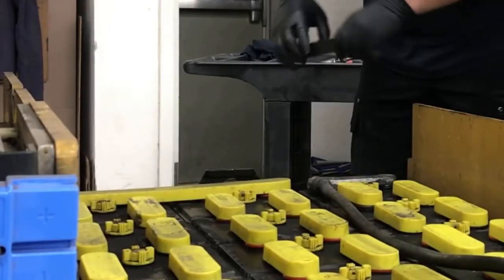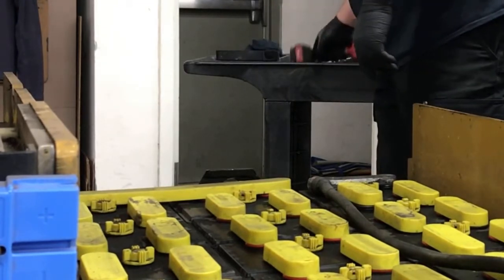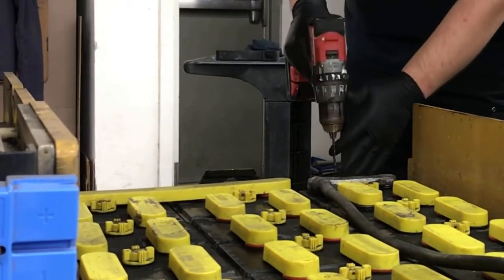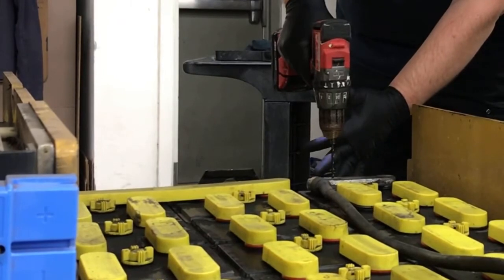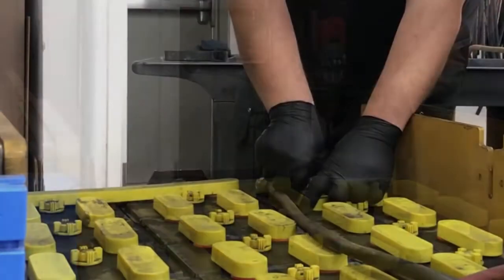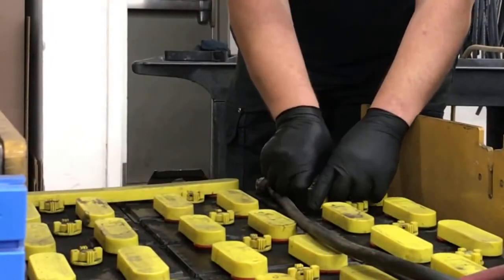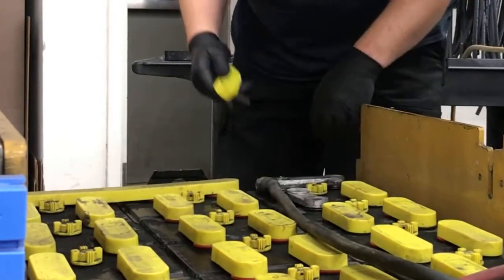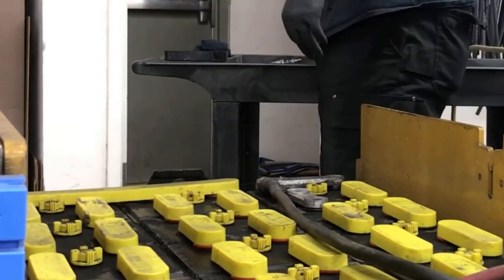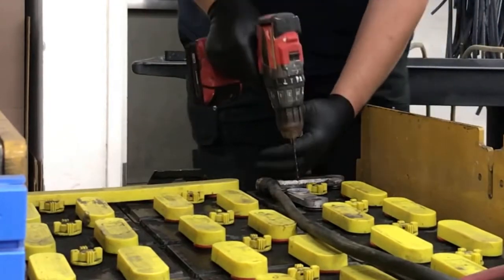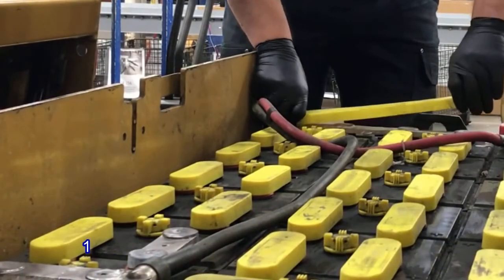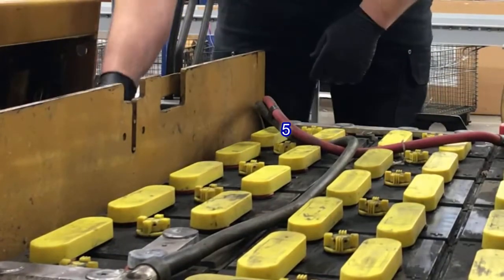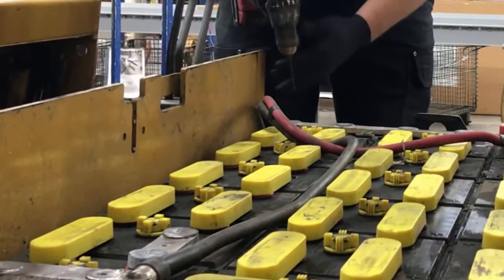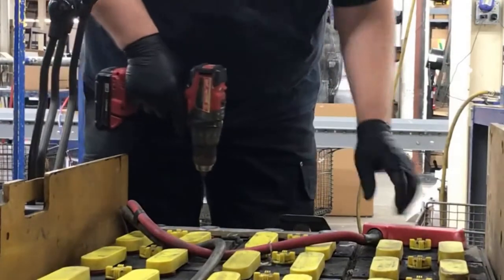Remove the cell cover and drill a 5/32 inch pilot hole in the battery negative post for the black wire. Then drill 5/32 inch pilot holes in the battery strap for the brown and orange wires and the thermistor. Then at the 6th cell from the battery negative for the blue wire, and at the battery positive for the red wire.